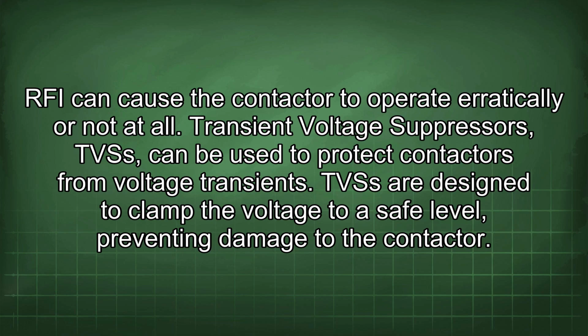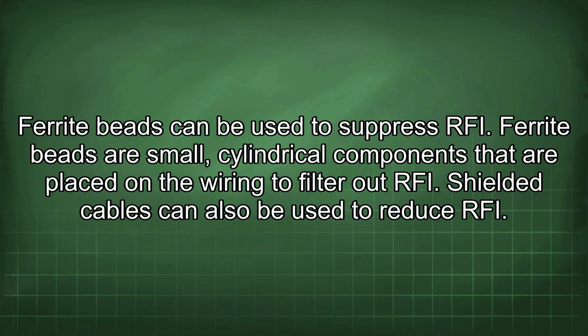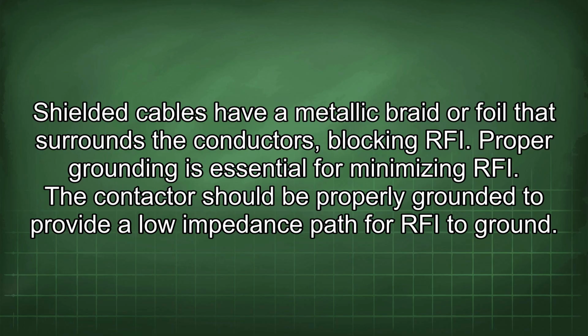Transient voltage suppressors (TVSs) can be used to protect contactors from voltage transients. TVSs are designed to clamp the voltage to a safe level, preventing damage to the contactor. Ferrite beads can be used to suppress RFI. Ferrite beads are small, cylindrical components that are placed on the wiring to filter out RFI. Shielded cables can also be used to reduce RFI. Shielded cables have a metallic braid or foil that surrounds the conductors, blocking RFI.